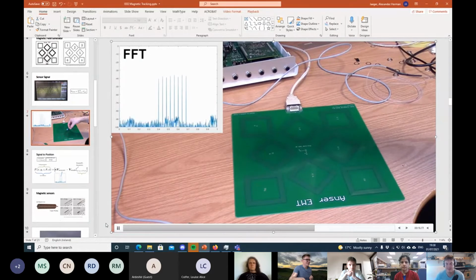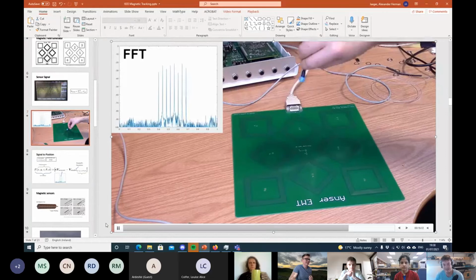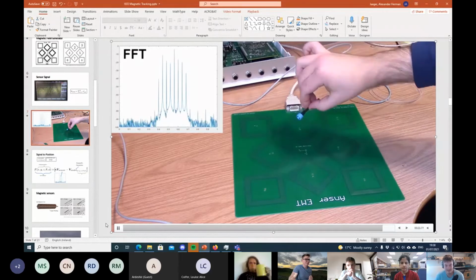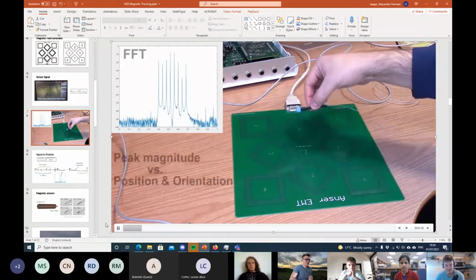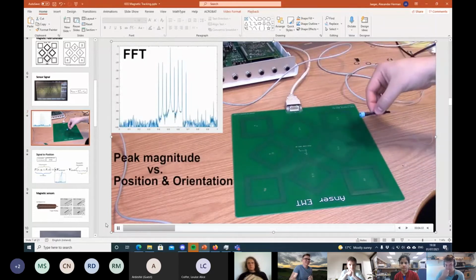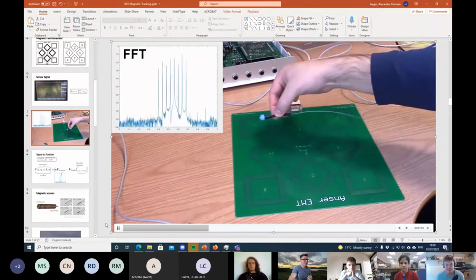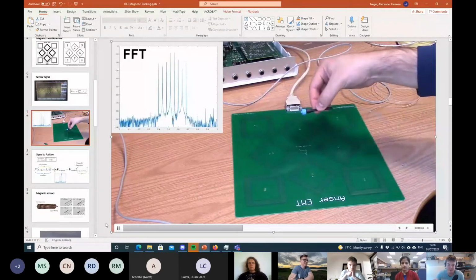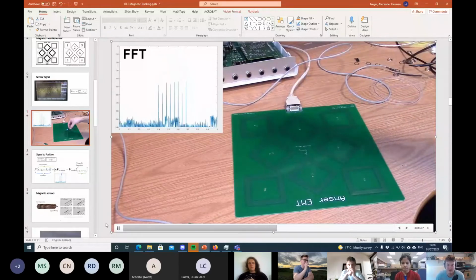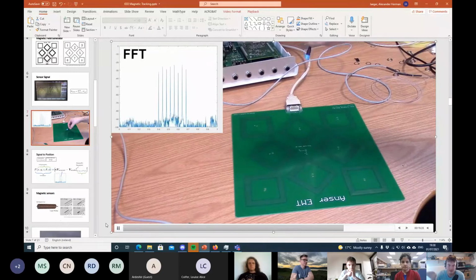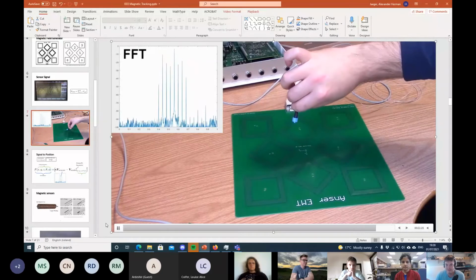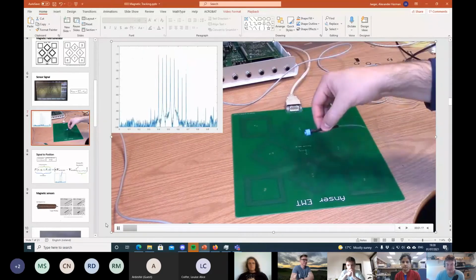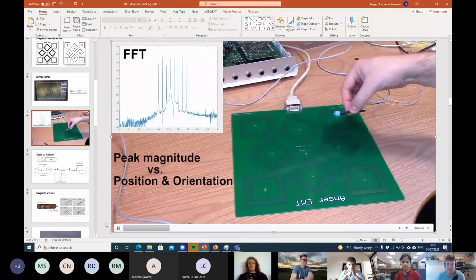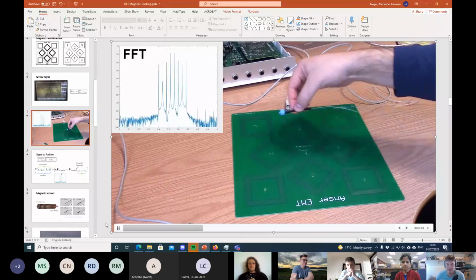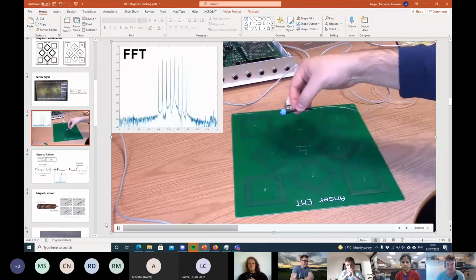I wonder if you could use the sidebands as a velocity measurement, to confirm you've moved a millimeter based on the velocity per second. We've looked at that. It's fairly easy to see when you're close to the field generator and your magnitudes are strong, but once you get further away, the leakage drops below the noise floor, so you can't measure anymore and the velocity measurement doesn't work. Up close it works quite well, but far away the leakage doesn't work anymore.